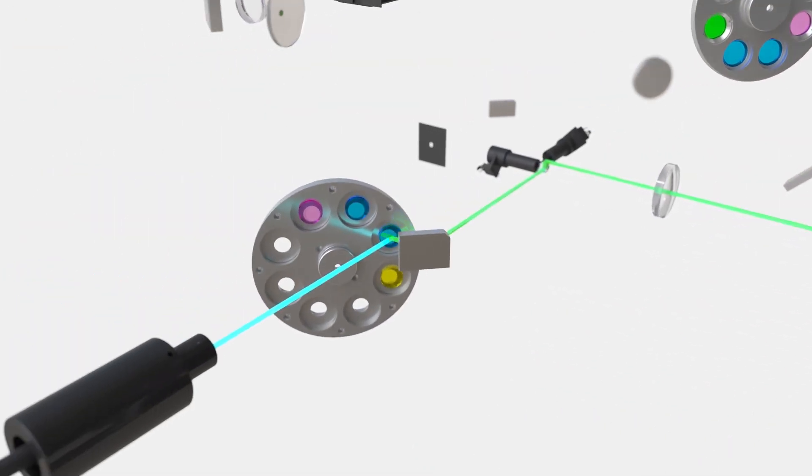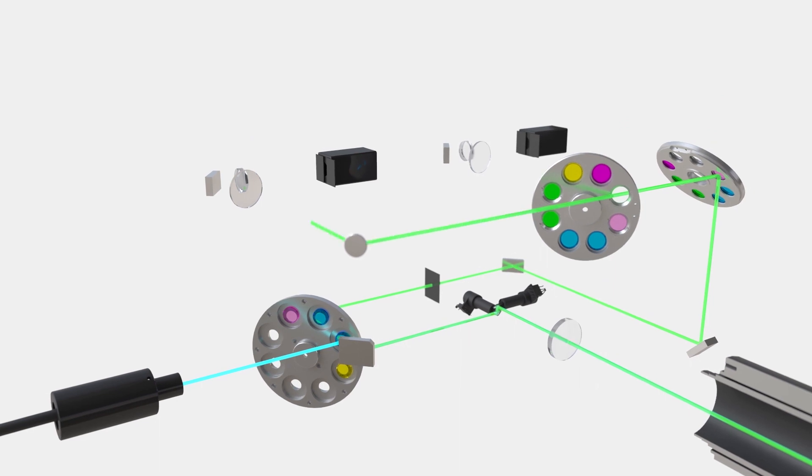Emission light passes back through the scanner along the same path as the excitation light, passing through the excitation dichroic and up to the TrueSpectral detector deck.